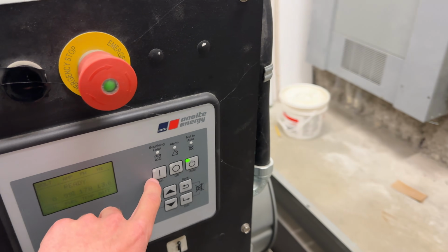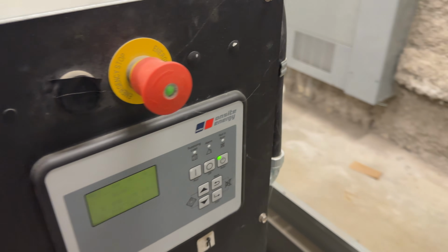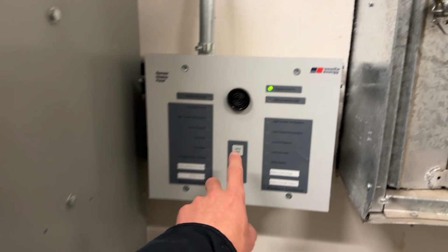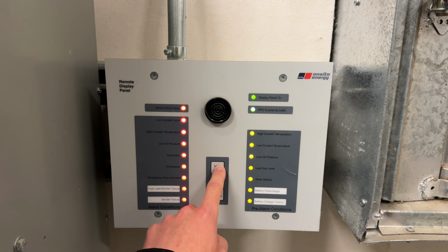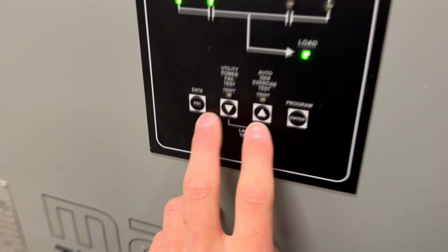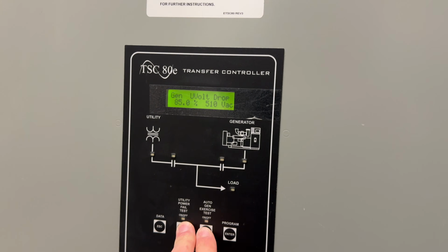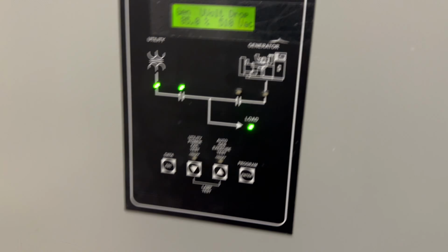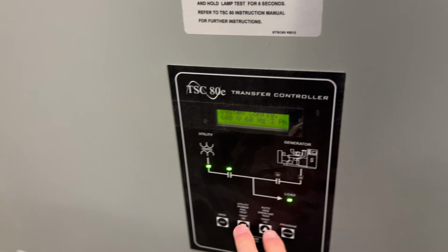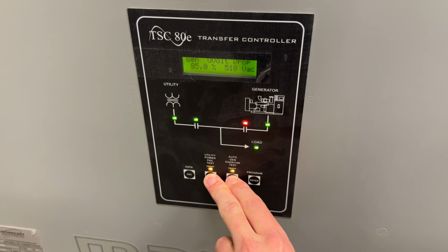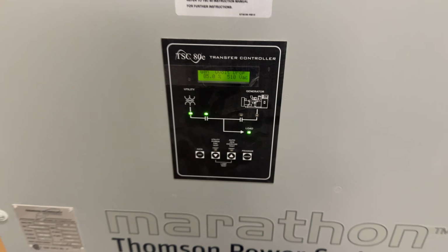If I was to take the generator out of auto and put it in run or off, that would now be on. So I will show the lamp test on here. You can see that is working. And on here, lamp test is if you hit both these, lights up everything, all good. Same with this transfer switch here. Lights up everything, all good.